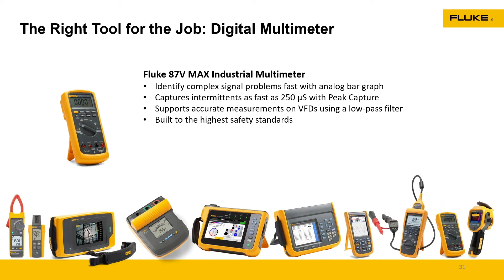Now, another component, and I talked about this when we were doing the job in Oregon, is a good insulation tester. Based on the voltage and the output, you may only need to go up to 1,000 volts. In some cases, you need to go higher. There's a good practice when we start talking about insulation testing, and it's basically to double the rating, or double the voltage output, of what the cable is rated for. What I mean by that is that typical Romex wire that we use for our homes is typically 14 gauge 2-wire with a ground. We put 120 volts on it in our house, in our commercial businesses. That cable is actually rated for 600 volts. If we wanted to do an insulation test on that, we would want to put 1,200 volts against that, or if we needed to, we would do it at 1,000 volts for a longer test.